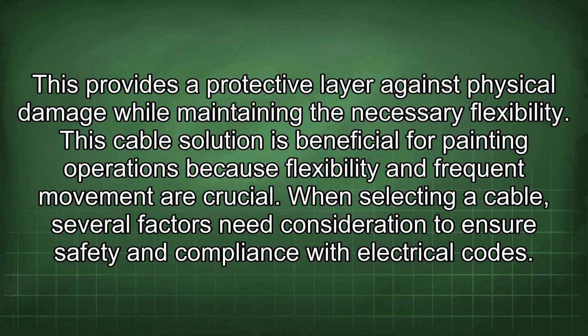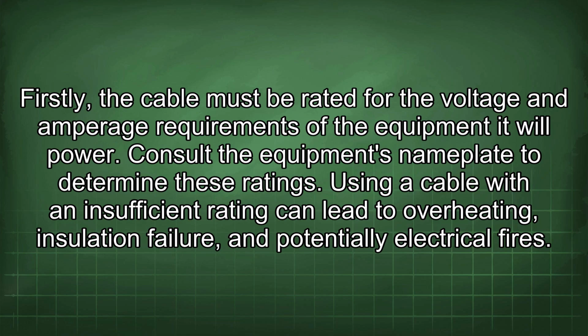When selecting a cable, several factors need consideration to ensure safety and compliance with electrical codes. Firstly, the cable must be rated for the voltage and amperage requirements of the equipment it will power. Consult the equipment's nameplate to determine these ratings. Using a cable with an insufficient rating can lead to overheating, insulation failure, and potentially electrical fires.